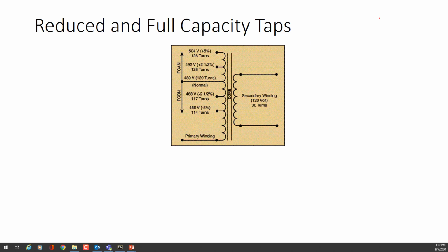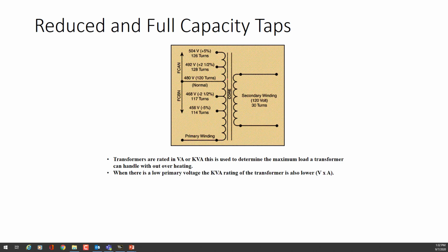So when you do see these transformers, they're going to be marked out for you. And on the nameplate, you're going to have, obviously, its VA and kVA. So that'd be its maximum load for the transformer. We're also going to have its voltage rating. So when there's a low primary voltage, the kVA rating of the transformer can also be reduced. So volts times amperage. If I reduce the voltage and still multiply it by the same rated current of that transformer, the kVA of that transformer can be reduced. So not always. You have to really pay attention to the taps and the tap labeling.